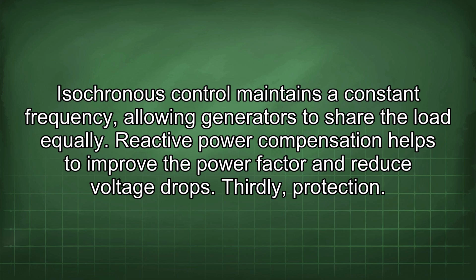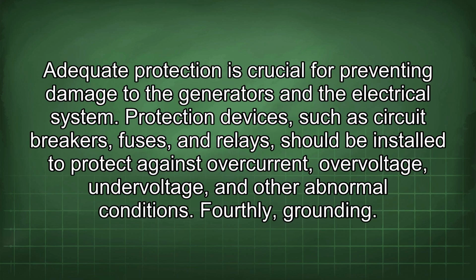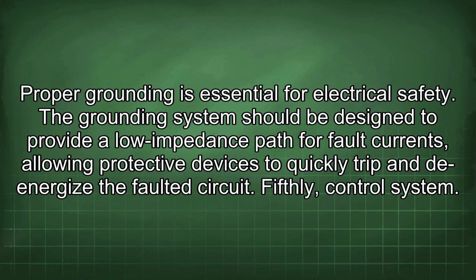Thirdly, protection. Adequate protection is crucial for preventing damage to the generators and the electrical system. Protection devices, such as circuit breakers, fuses, and relays should be installed to protect against overcurrent, overvoltage, undervoltage, and other abnormal conditions. Fourthly, grounding. Proper grounding is essential for electrical safety. The grounding system should be designed to provide a low impedance path for fault currents, allowing protective devices to quickly trip and de-energize the faulted circuit.